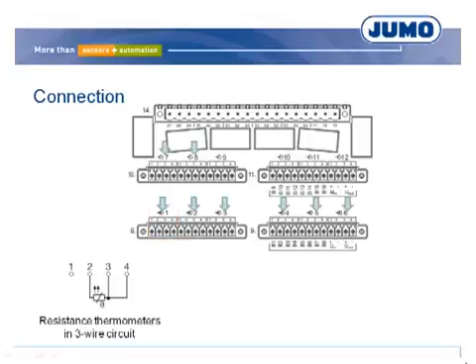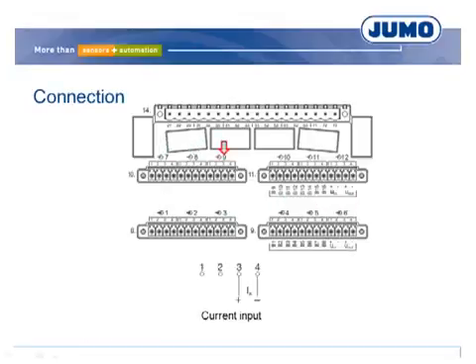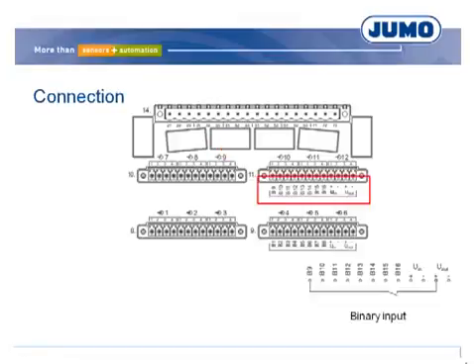The temperature values are measured via a resistance thermometer PT100 in three-wire circuit. The signal of the humidity sensor is 4 to 20 mA. A contact on binary input 9 shows the condition of the magnetic valve.